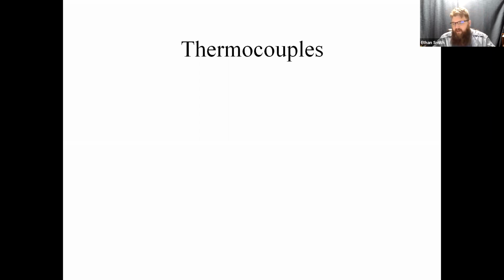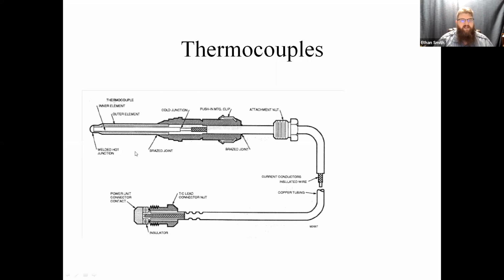Okay, let's talk about thermocouples because they're a little different. Thermocouples are kind of fun little devices, and at their root, all they really are is two pieces of metal. We've got what we call an outer element and an inner element. All they are is two different types of metal. Usually we have a stainless steel on the outside and some type of copper alloy inside. And they're welded together at the tip of this flame sensor.